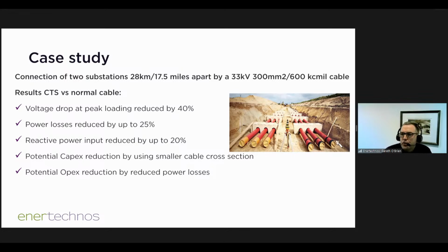Because the voltage is supported at the far end of the cable, we need to pull less current to deliver the same power. The effectiveness of this cable is typically measured in terms of additional power delivered through either the same amount or a smaller amount of copper. So you could go with a smaller cross-section cable, or the same cross-section and push more power through it.